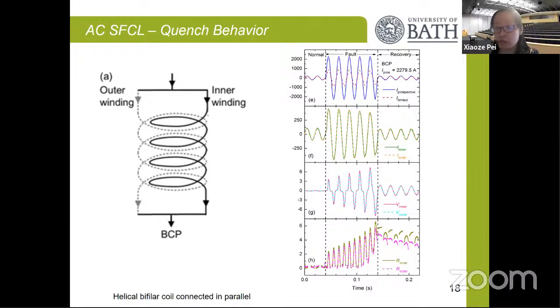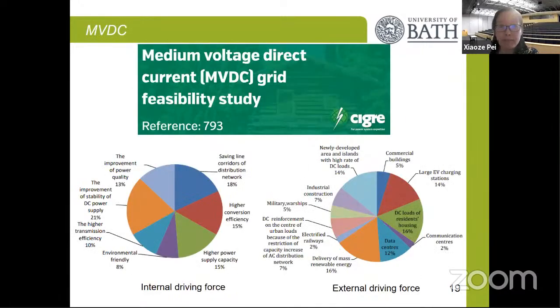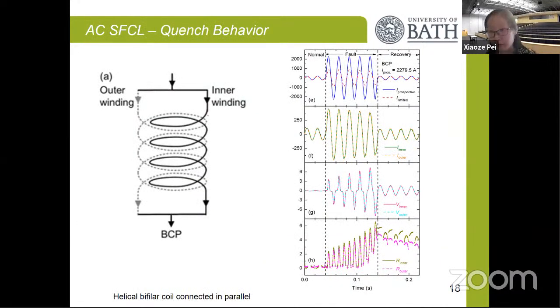So to summarize this section, we designed the superconducting fault current limiter, and examined in detail the mechanism, how to reduce the AC losses, what the quench behavior is, and also how it responds to different recovery conditions. Those provide very important guidance for the design of the superconducting fault current limiter. So I will draw a close for the AC part, which is the more conventional AC grid.